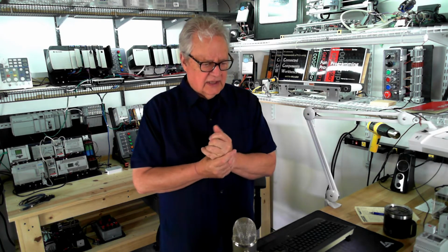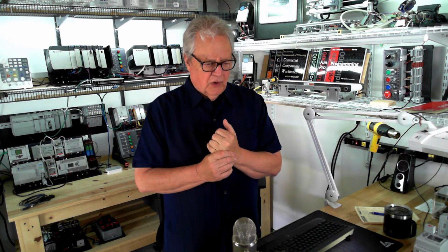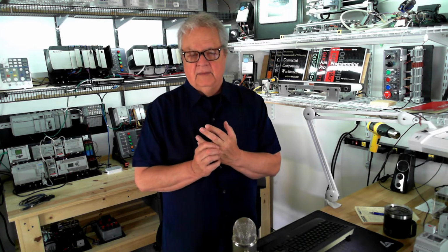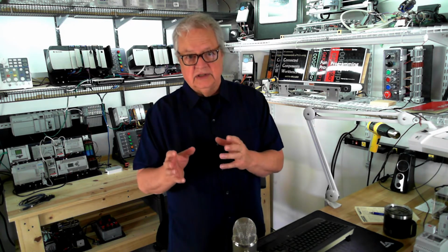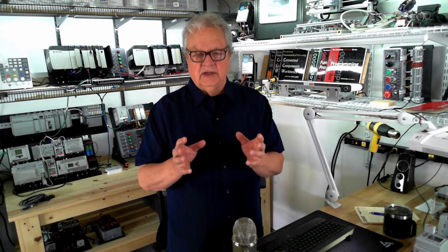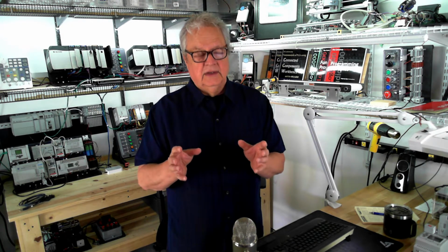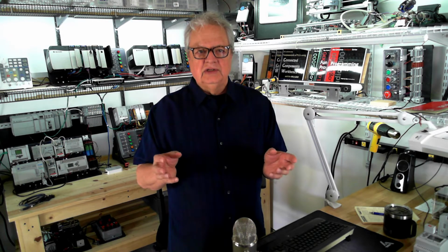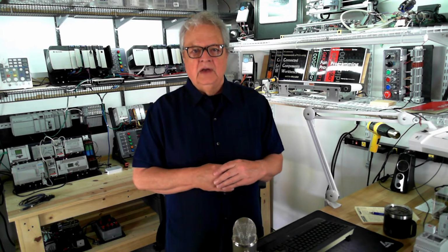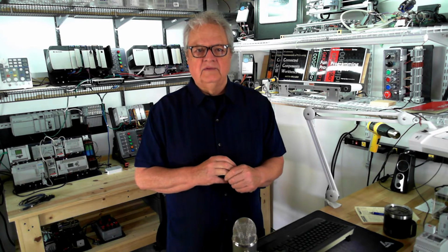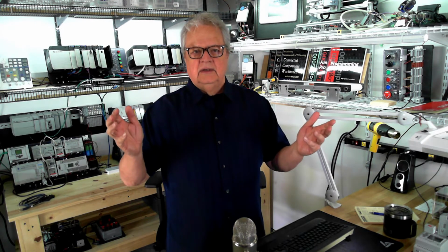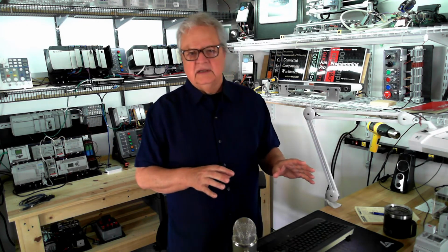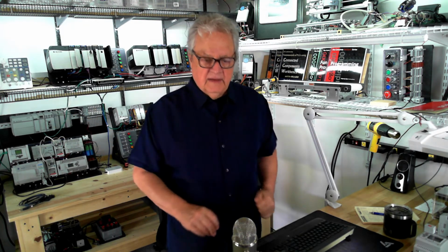Okay, so let's get into this lab project. We're also going to consider some other variations in programming, like latch, unlatch, which is set, reset, versus seal-in logic. Now remember, seal-in logic is the best. When you start using latches, then you have to unlatch the whole world, because it's easy to latch something in Cincinnati and you're in Chicago when you realize that you left it latched. Now you got to figure out how to unlatch it. That just means that this stuff can get spread out all over your program. With a little tiny program like this, it's not a big deal. So let's have at this.